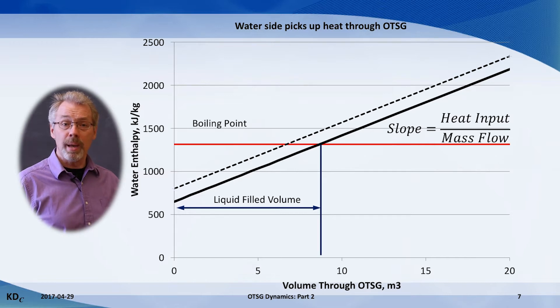Another operating change is to have an increase in the boiler feed water temperature. In this case, the water enters at a higher enthalpy, so for the same firing rate, the steam exits at a higher enthalpy and quality. This also results in a decreased water volume in the OTSG.